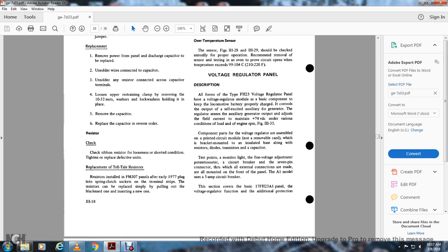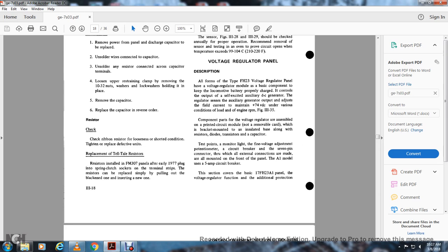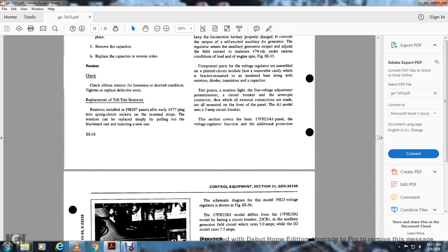Components of the voltage regulator: some of the printed circuit module is not a removable card in the bracket and insulated from the base, along with resistors, diodes, transistors, capacitors. Test points, monitor light, fine voltage adjustment potentiometer, and the circuit breaker, with a 7-pin connector for the external connections, are all mounted on the front panel. The A1 uses the 5 amp circuit breaker with the section cover, the basic 17FH23A1 panel with the voltage regulator function, and additional protection.